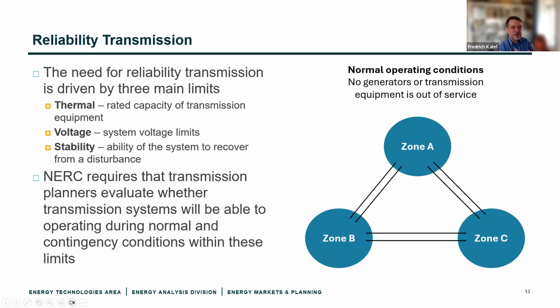For reliability transmission, the idea is that we need to maintain reliable operations of the transmission system within three main limits. The first is thermal, which is just the rated capacity of the transmission equipment - you can think of this in megawatt terms. If we have a 500 megawatt transmission line, we need to keep the amount of power flowing in that line below 500 megawatts.